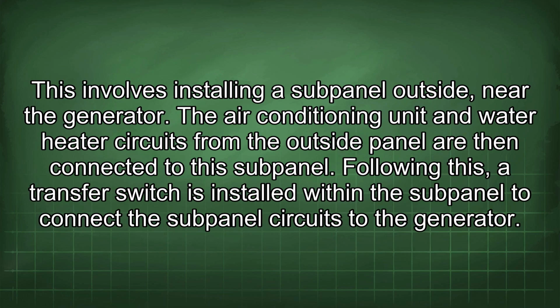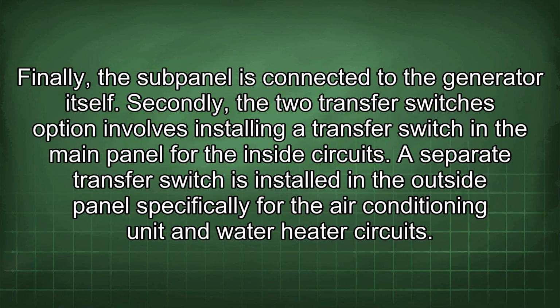This involves installing a subpanel outside, near the generator. The air conditioning unit and water heater circuits from the outside panel are then connected to this subpanel. Following this, a transfer switch is installed within the subpanel to connect the subpanel circuits to the generator. Finally, the subpanel is connected to the generator itself.